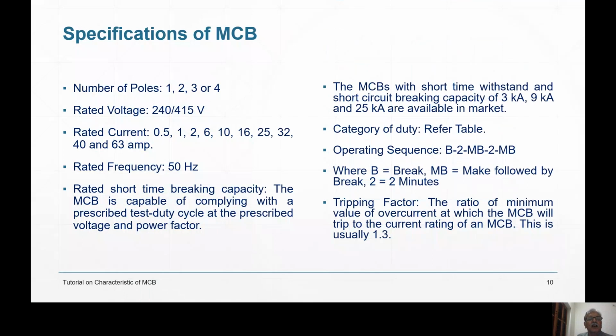Then I just wanted to give you an idea of specifications, how the MCBs are specified. You have to specify whether you want 1-pole MCB, 2-pole, 3-pole, 4-pole, how many poles you want. Then you have to specify whether you want 240 volt rating or 415. Beyond 450 it is not available. Rated current is 0.5 ampere to 63 ampere. You have to specify which current you want, right? Because if your equipment is taking 1.6 ampere or 1.8 ampere, you have to take 2 ampere MCB. That is very obvious. Rated frequency in India is 50 hertz.